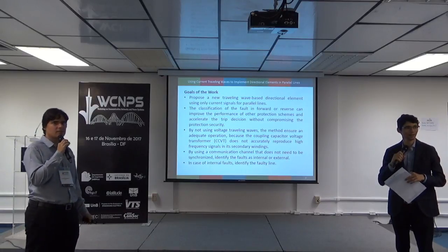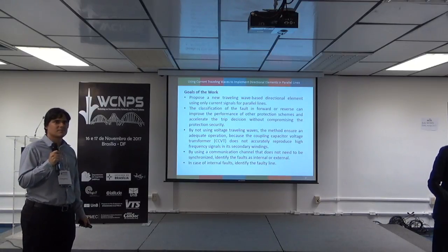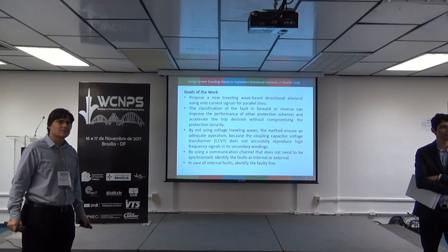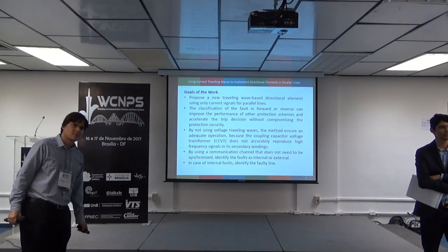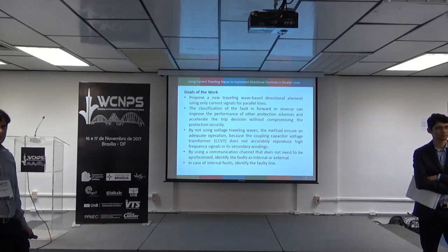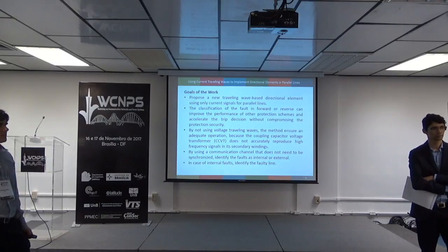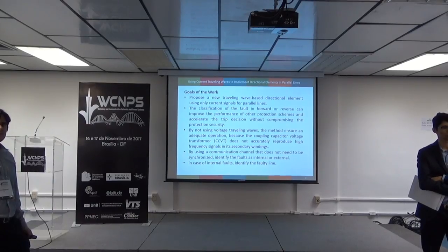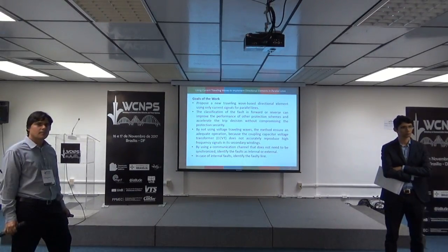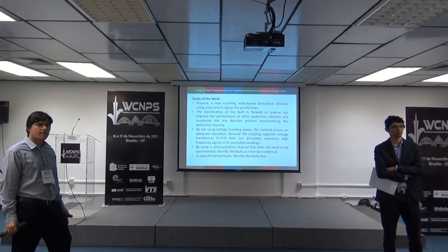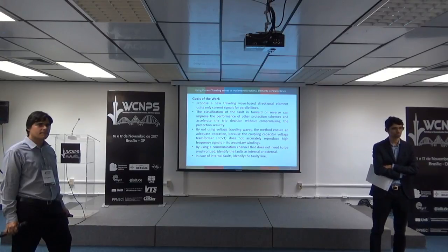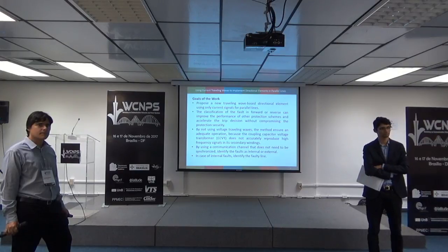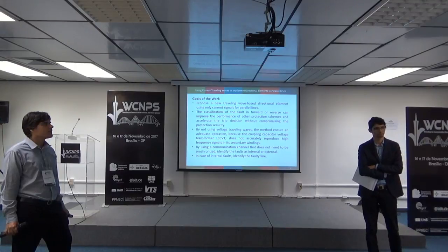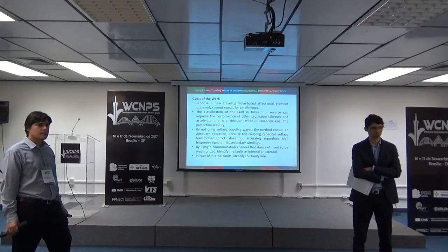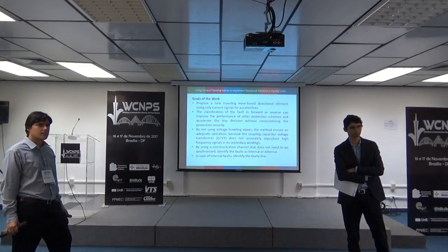Fernando was not in the work where we evaluated this kind of problem. He's working now using current traveling waves, but we have already evaluated this problem when we used CCVTs to measure traveling waves, and we have problems measuring the amplitude of these traveling waves, but the polarity of the first incident traveling wave is not lost, so we can use that. We already have some time domain relays which operate using these voltage traveling waves, but only the first voltage traveling waves. If you need the reflections, it does not work. So, we have problems. It attenuates the voltage transients.